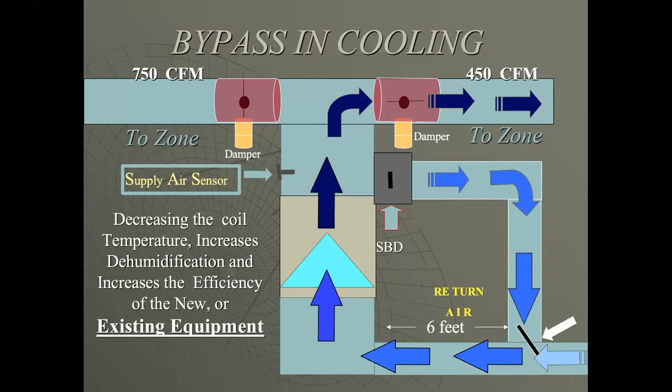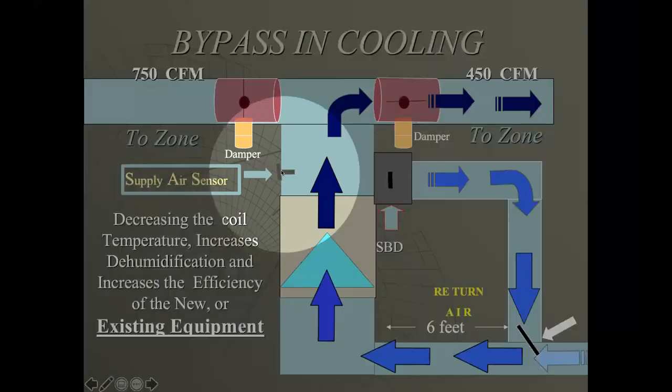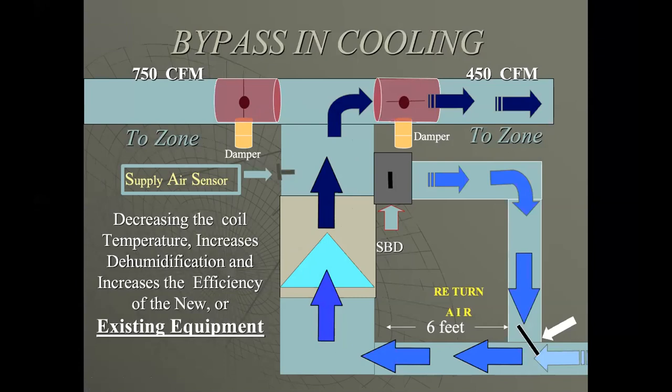One thing that EWC does, we have a supply air sensor that is packaged with every panel. I want to make sure that I'm not slugging liquid back to a compressor, freezing up a coil, going into inoperable temperatures. And I'll look at Houston, for the fact that this is where I see the majority of duct sweating situations because of our humidity. Well, we've got one particular company that will drop their supply temperature down to 40 degrees. Well, you take 40 degrees through a duct in that Houston market, I'm sorry, you're going to have not only the duct sweating, the cabinet sweating, you'll have everything sweating.